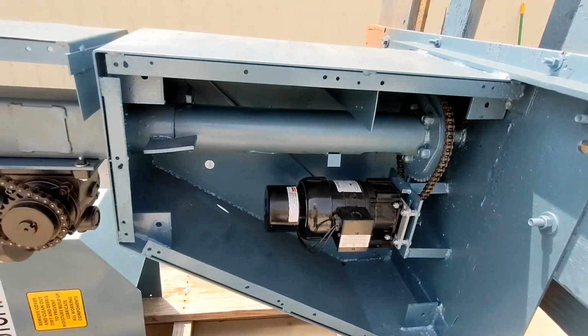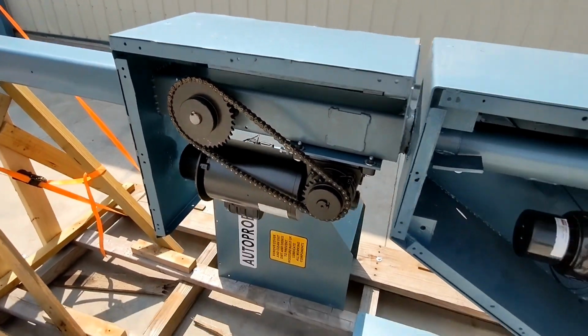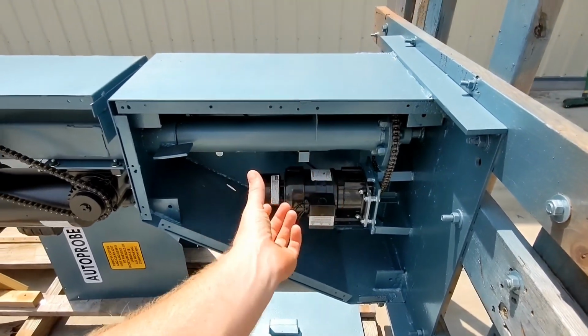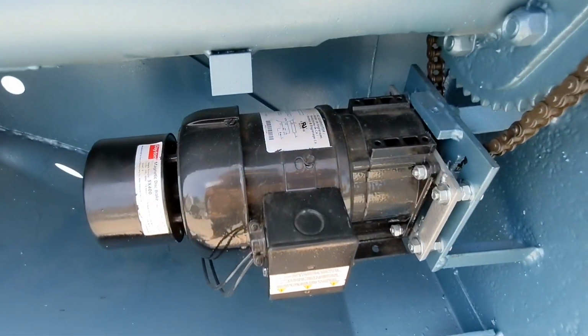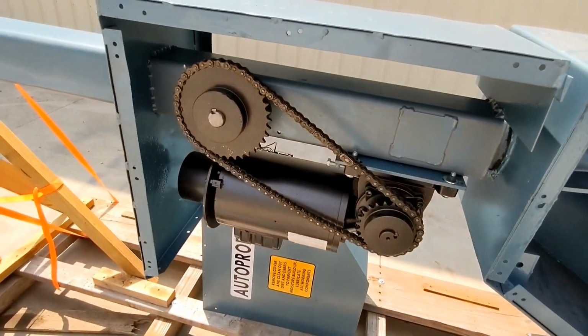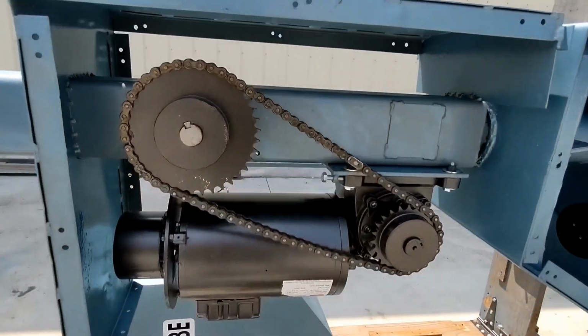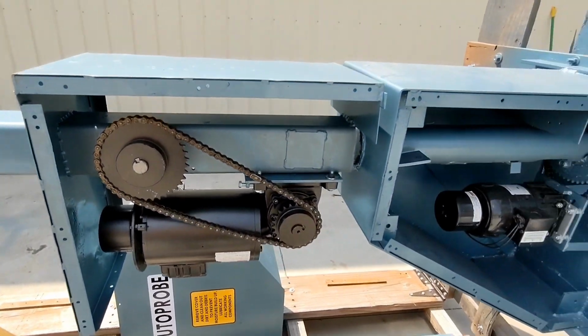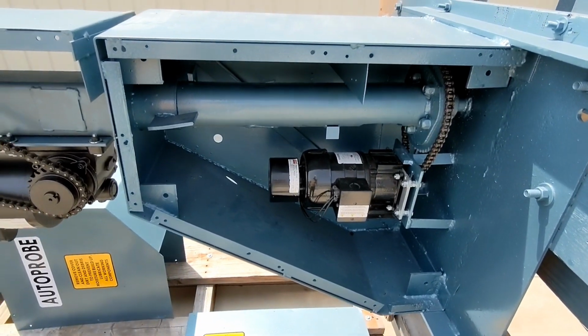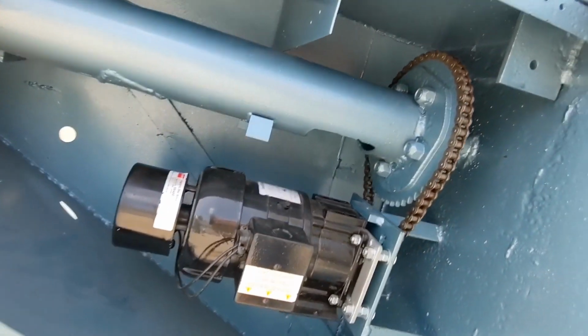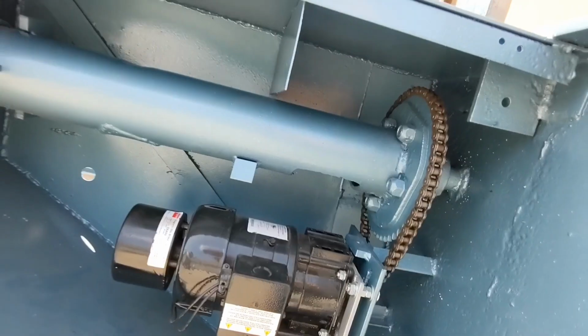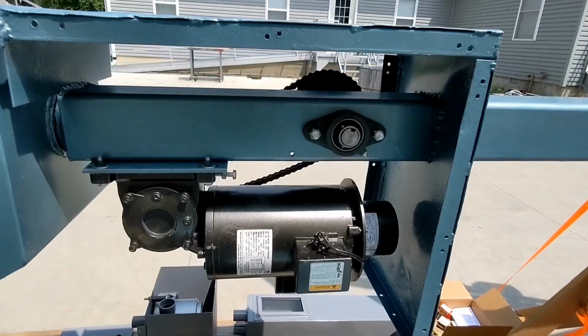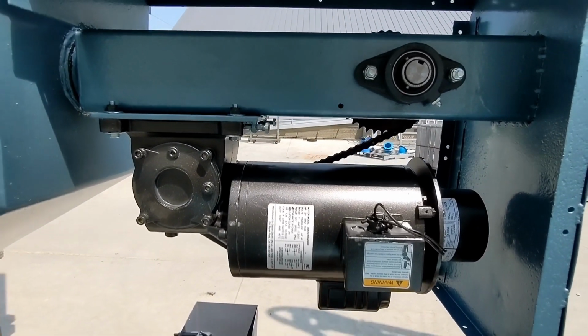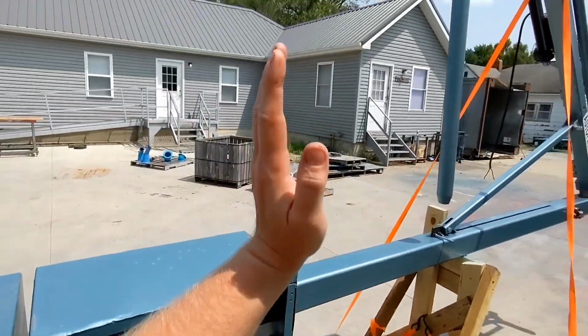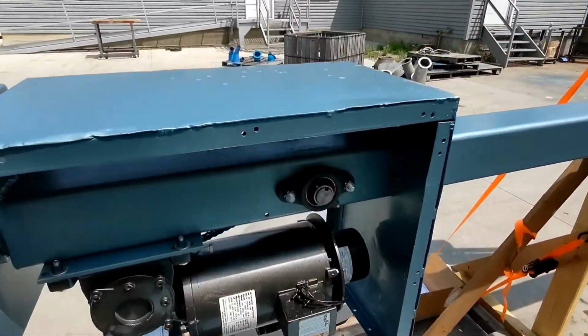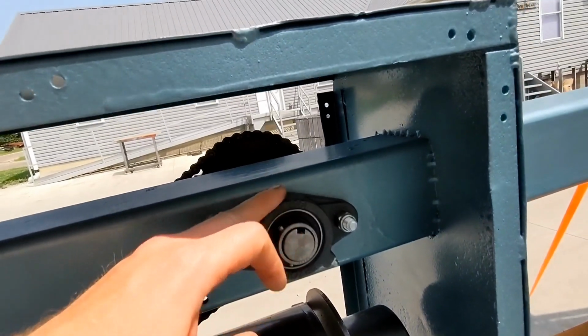Both of these motors, the boom extension motor and the probe swiveling motor, are run off of single phase 110 volts. You can see the listing for a picture of the motor tag so you can take down any pertinent information. The main bearings on this unit have been serviced, have been checked over and inspected for wear. They're in good condition. You can see the opposite side of the boom control motor. This is the motor that controls the boom going up or down. We put new bearings on the column here.